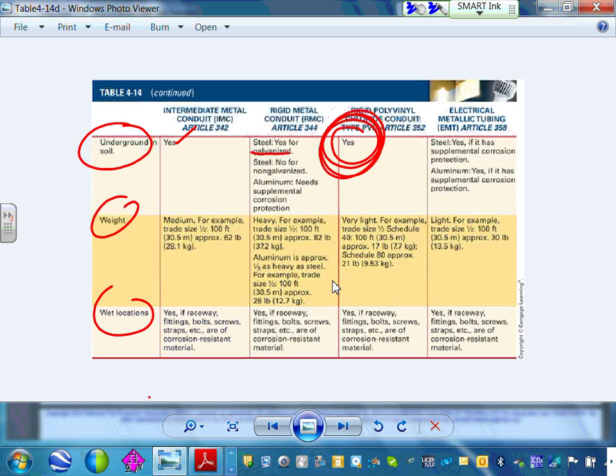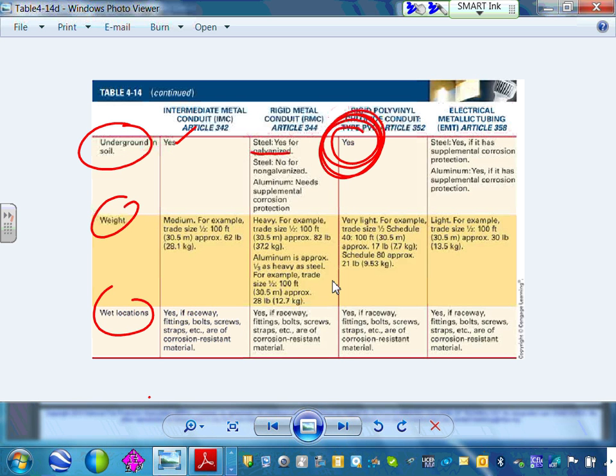Wet location - can you put all of them in wet location? You can see they're rated for wet location, not direct buried. Wet location, like outdoor in the wall right here, above ground. They're all listed for above ground. But if you're in wet location, which one is above ground wet location? The cheapest above ground wet location, no physical damage - which one is your conduit of choice?